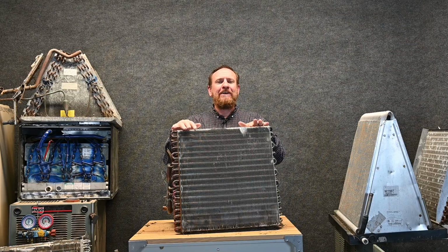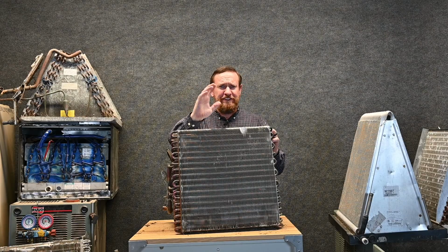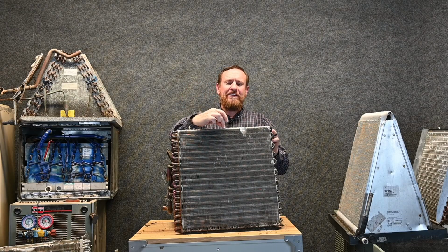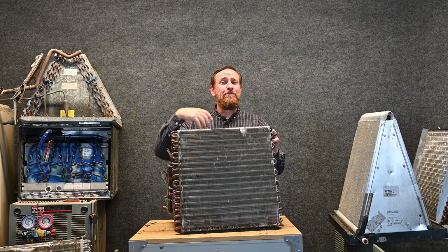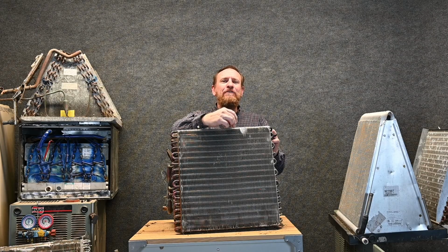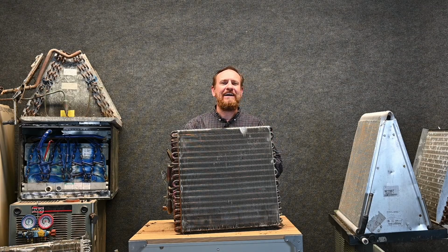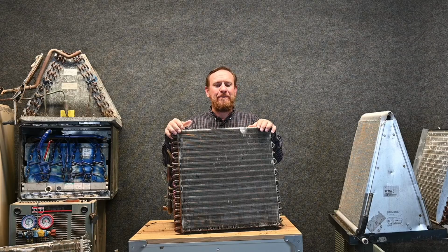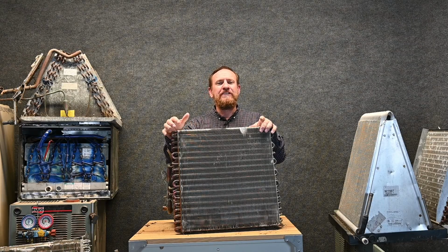So let's talk about some of the things that cause leaks. I've talked to some manufacturers about leaks, and they say that they've done spectral analysis, or some fancy word, and they've found out that chemicals from the house, so we have more chemicals in the house than we've had before, start reacting with the copper, and it starts having pinhole leaks from the outside to the inside. And that's one of the issues they say is happening. Other manufacturers I've talked to said that they've done tests.